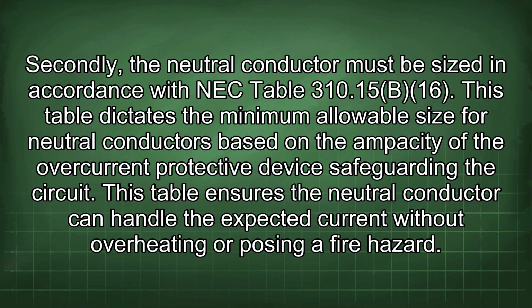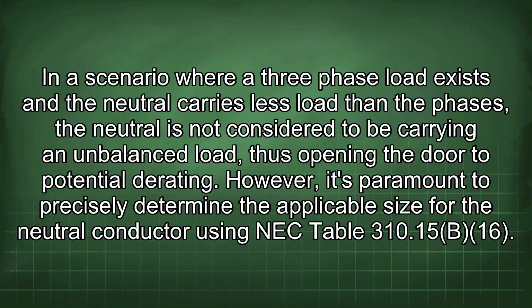Secondly, the neutral conductor must be sized in accordance with NEC Table 310.15(B)(16). This table dictates the minimum allowable size for neutral conductors based on the ampacity of the overcurrent protective device safeguarding the circuit. This table ensures the neutral conductor can handle the expected current without overheating or posing a fire hazard. In a scenario where a 3-phase load exists and the neutral carries less load than the phases, the neutral is not considered to be carrying an unbalanced load, thus opening the door to potential derating.